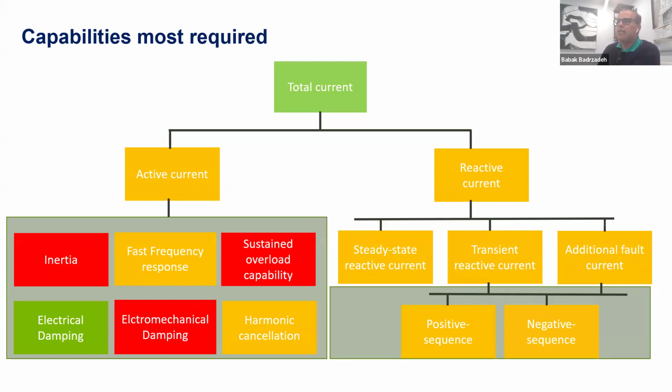And before I show that, the same categorization and prioritization of current that I had shown in the previous slide. Now you see that the colors have changed a little bit, and the philosophy is still the same. Let's say you have 100% rated current during transient condition, and that's not exaggerated, like I said. And as you saw in the previous slide, many OEMs confirm that whether the transient overcurrent is 120% doesn't really change the picture.